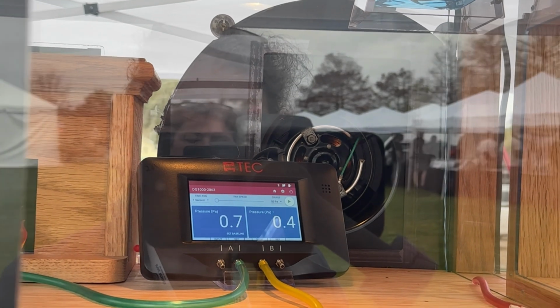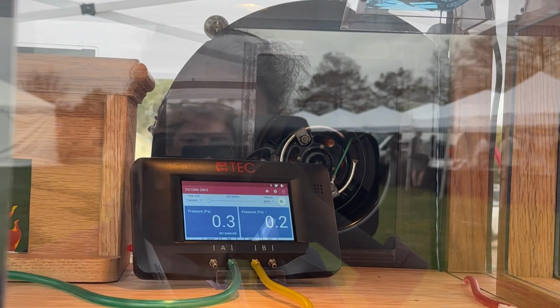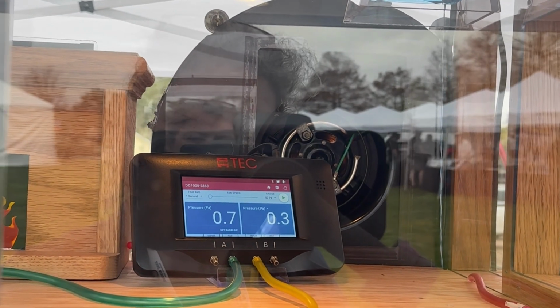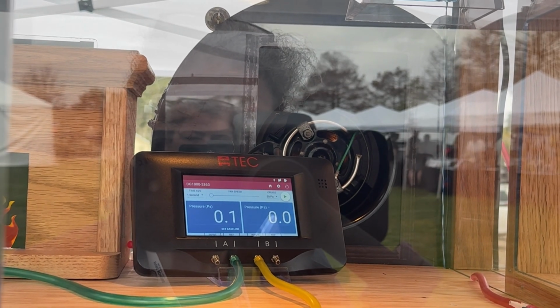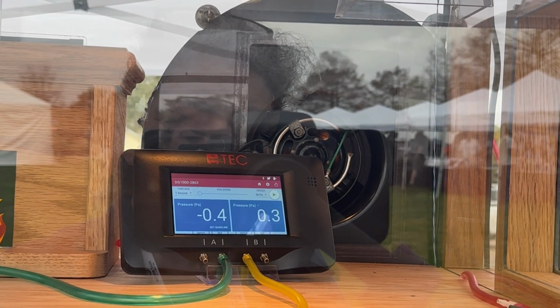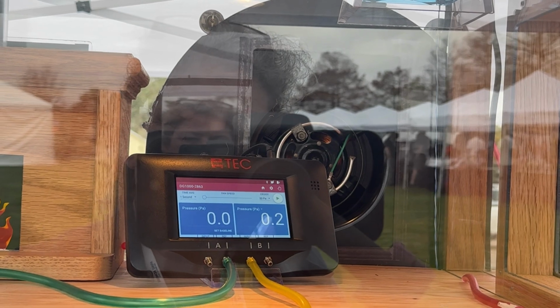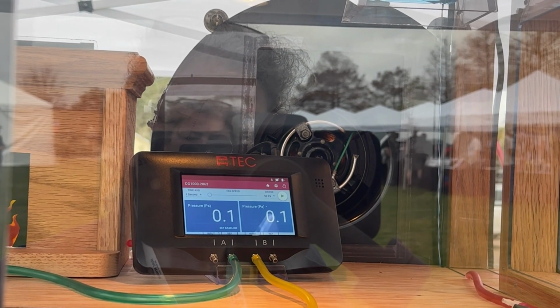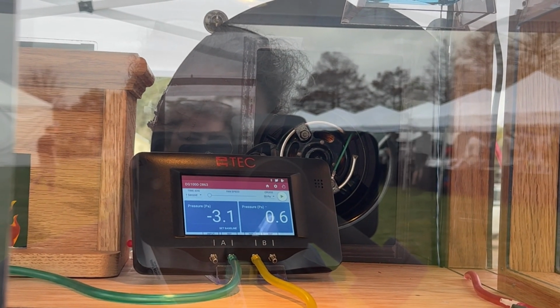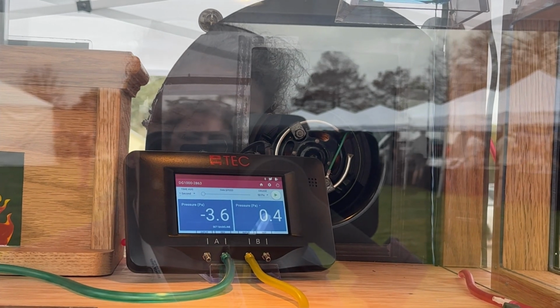It's like 0.2. Now keep your eye on the screen, but I'm going to go back to where we were before and make that leak. Now part of that supply air that was blowing in is going to blow into your attic or crawl space or wherever that leak is. Watch what happens to the pressure here. See how it changed? Wow, it's negative 3.6.